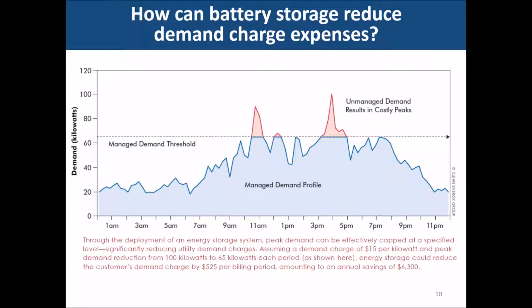The red areas are showing cases where the battery is actually discharging to hold the peak demand at a managed demand threshold. So basically the battery is saying, whenever demand approaches this threshold, we're going to discharge the energy in that system to make sure that demand doesn't go above that level, and we hold our peak demand at around 65 kilowatts instead of going up in the 100 kilowatt range.